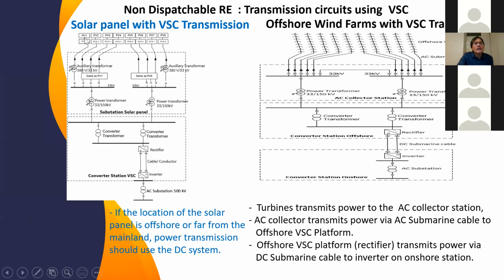How does it work? Imagine this is photovoltaic. We connect to the PCS inverter. From the inverter, we connect to the solar panel substation using cable or conductor. And then we have an auxiliary transformer here. From the auxiliary transformer, we increase the voltage up to 150 kV in the solar panel substation. And then we transmit the power to the converter station. Here, rectifier. This is the converter station. So from the rectifier, we can transmit the power through cable or conductor to the inverter. So we do not have a problem with distance here.